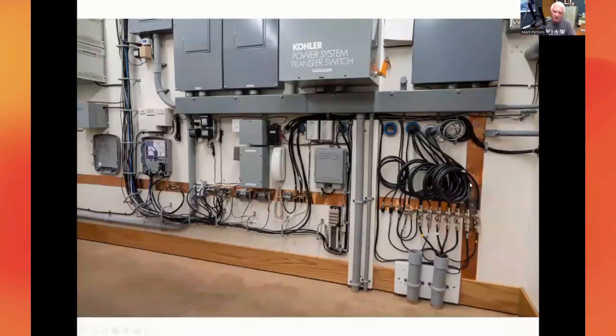Now, I showed you not a very good view before, but this is more detailed. This is below the 240 volt part of the installation. And what you see here is a copper strap. That is a common point ground. There are multiple ground rods outside the house that tie into this first electrical panel. And that panel has this copper strap on it. And then the strap goes all over here and over to the rack.